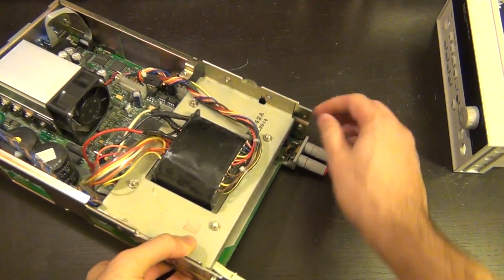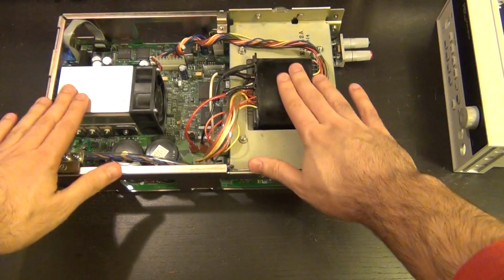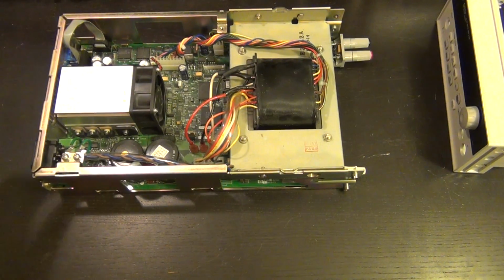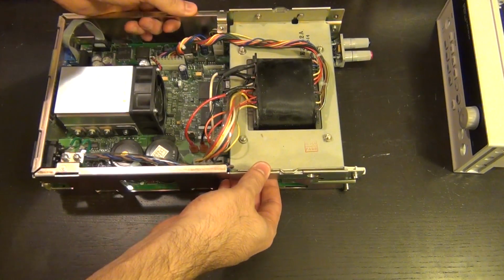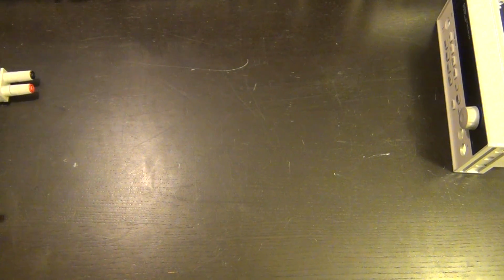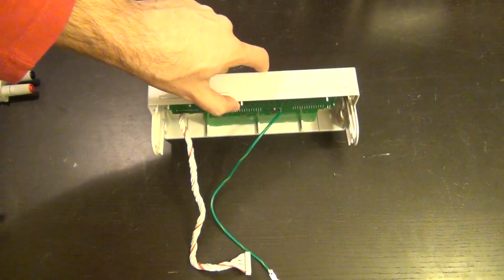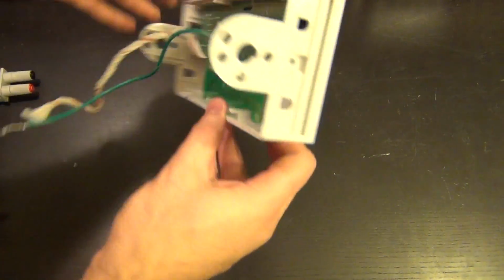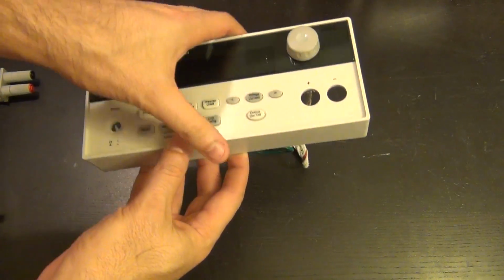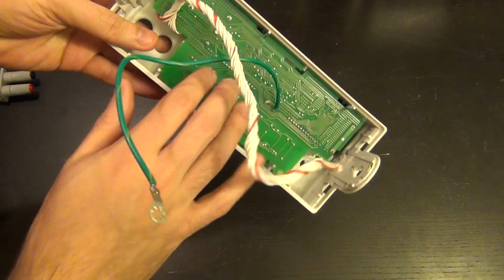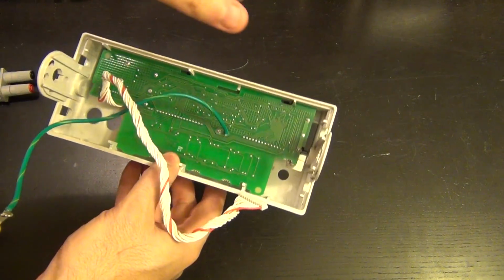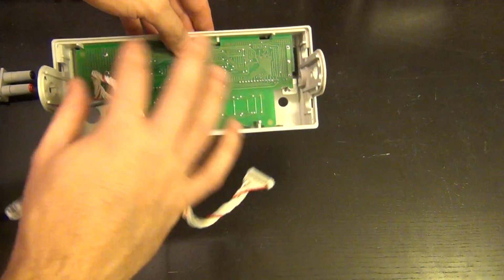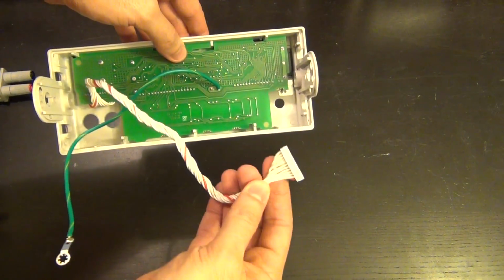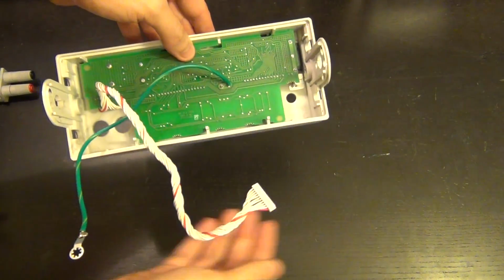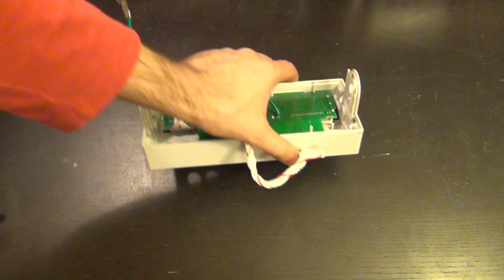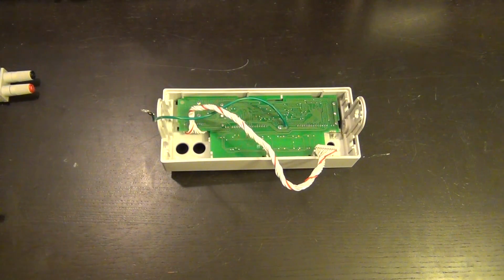So at least from our new measurements and the tests that we did, this part is fully functional. It seems to be working. I did some more measurements, voltage and currents and so on, and it's dead on. It doesn't even need to be calibrated. And so here we go. This is now the focus of our attention. We have to disassemble this and figure out what's going on. There's a whole bunch of circuitry in there. Obviously, because the instrument can tell that there is no communication coming from this, there must be a processor in there that handles some kind of serial or parallel interface to the main board, which does everything that needs to be done. So there you go. That's our problem. Let's go ahead and see how we can disassemble this.